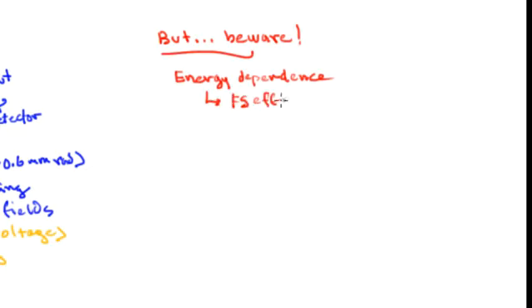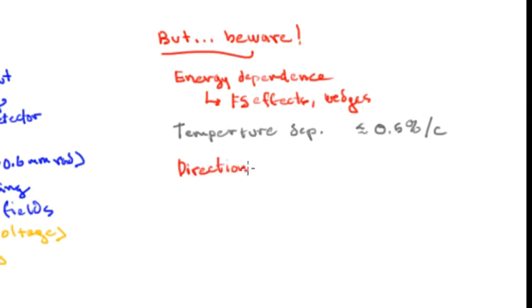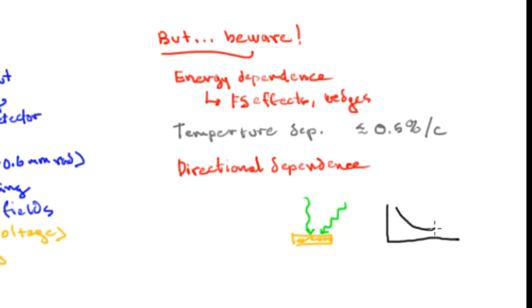There are several practical manifestations: there's a field size effect dependence, the detector will respond differently in wedge beams versus open beams, and there are other situations. These detectors also have a temperature dependence, about 0.5% per degree centigrade. They have a directional dependence—when the beam comes in at an angle, it will respond differently. If I draw a picture of the diode with the beam coming down straight or sideways, you can see the response shows an over-response of about 5% at a 45-degree angle.